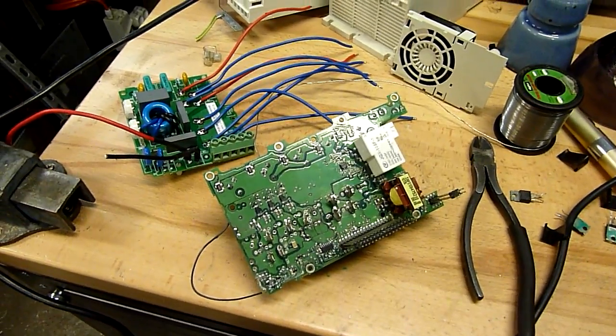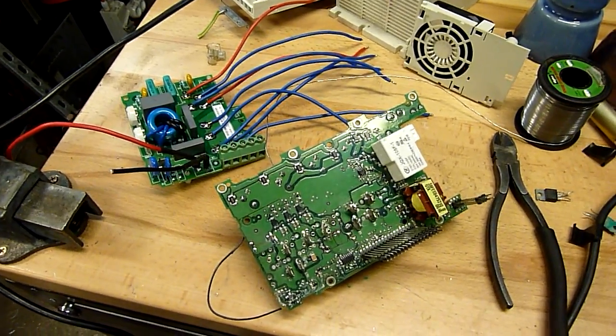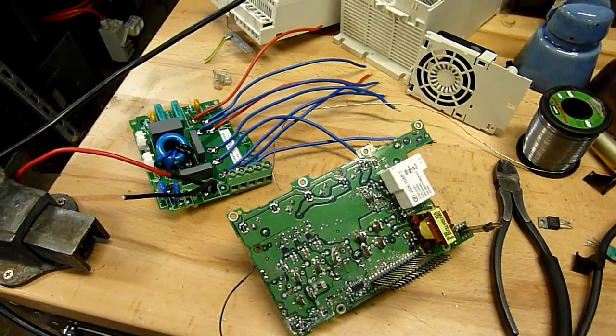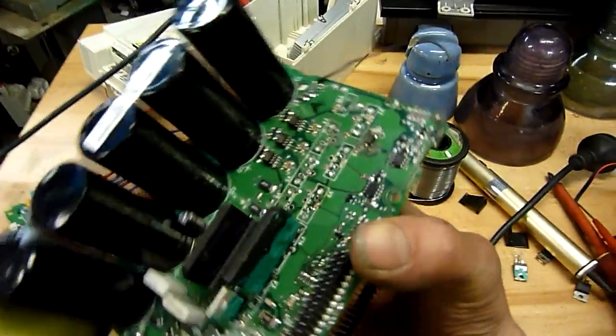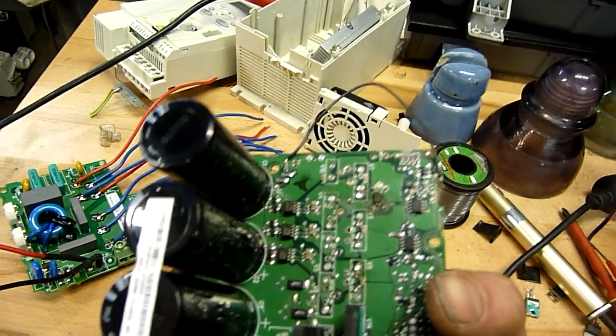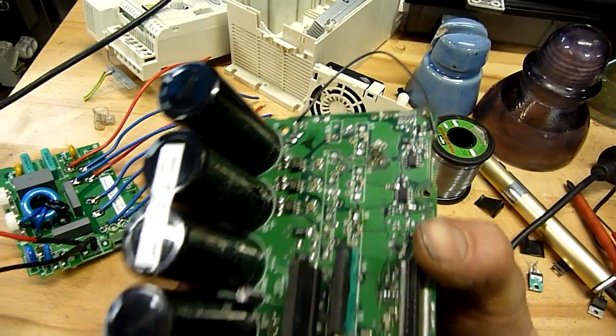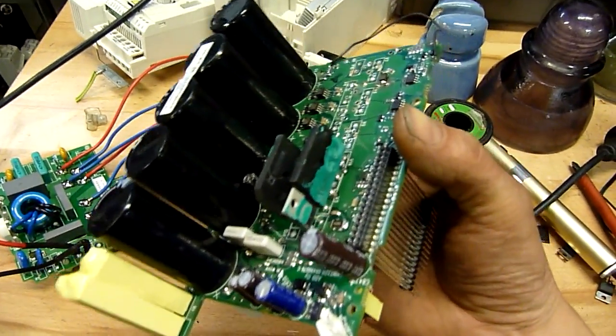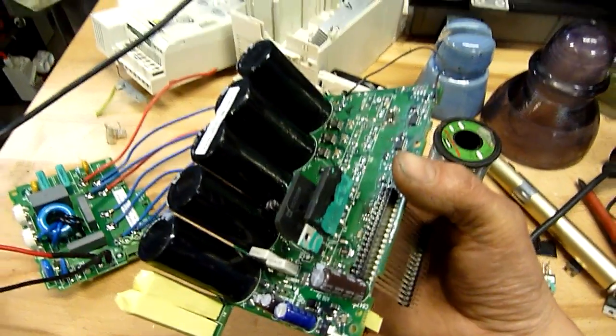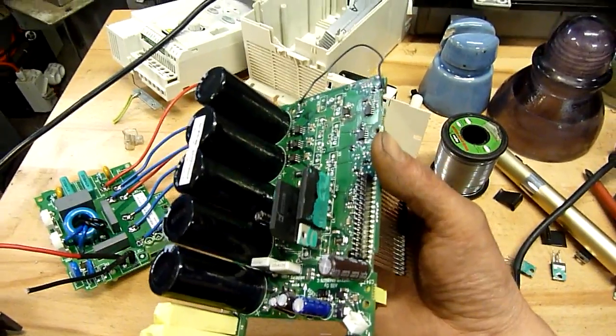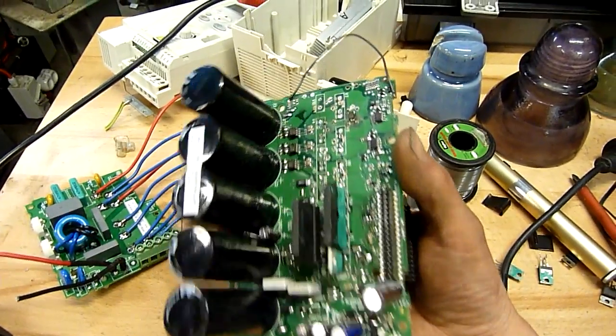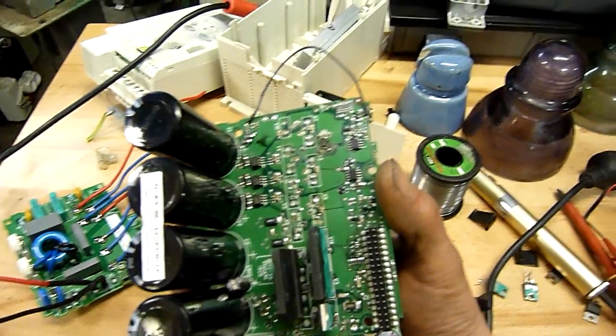I thought I'd eliminated the short, but I only eliminated the short on one of the phases. Even with them all removed, I found out these bridge rectifiers are completely blown. So something horrible has happened to this drive.